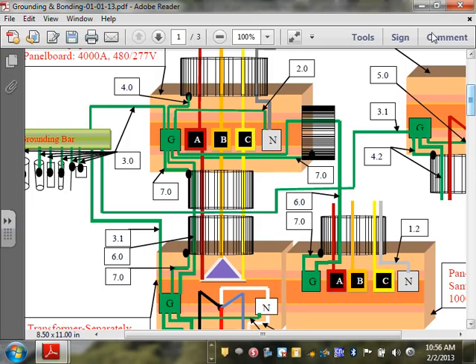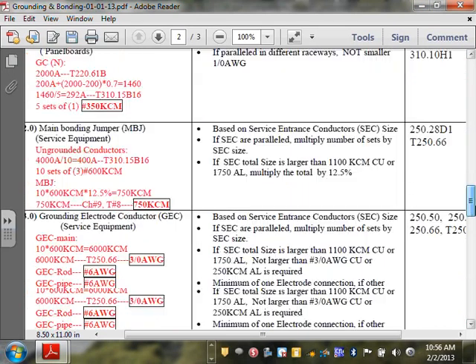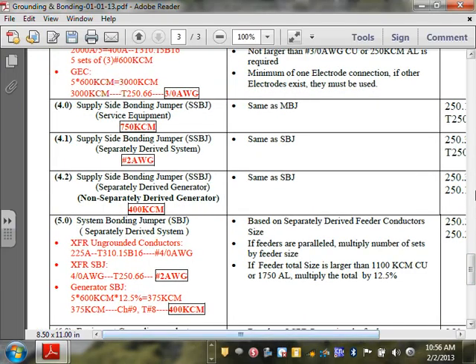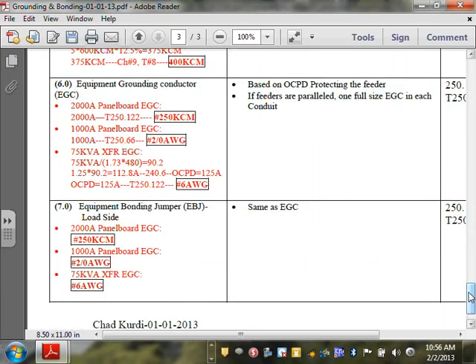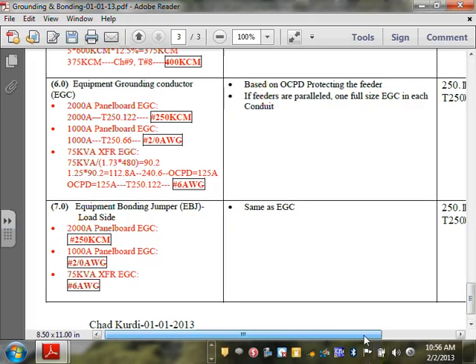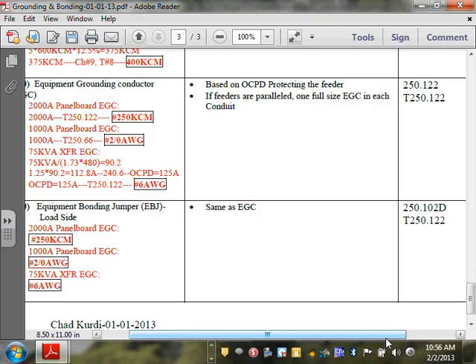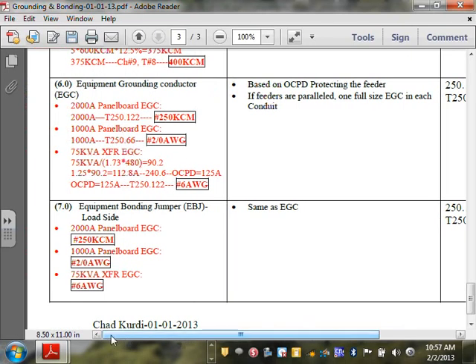I'm going to flash you to number 7, way at the bottom. So remember, here's number 7 here and here on both sides of the conduit. So if you guys go all the way to number 7, this is how it tells you. Number 7, only look at the 1000, will ya? Number 7, 1000, it says same as equipment grounding conductor. So don't even worry about it. Same as equipment grounding conductor, and it's 2/0 AWG. And where did they get this one? Again, I like to always flash the code, and here's where it tells you that's what you need to do. Any comments, guys? Any questions?